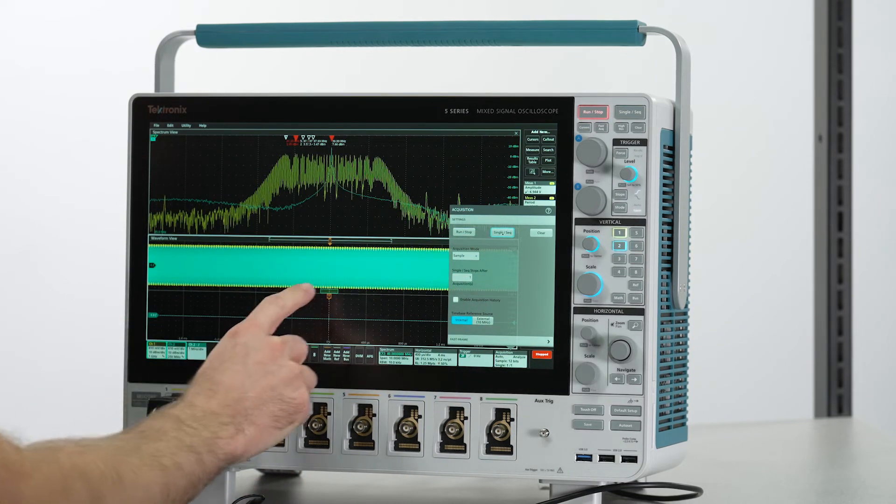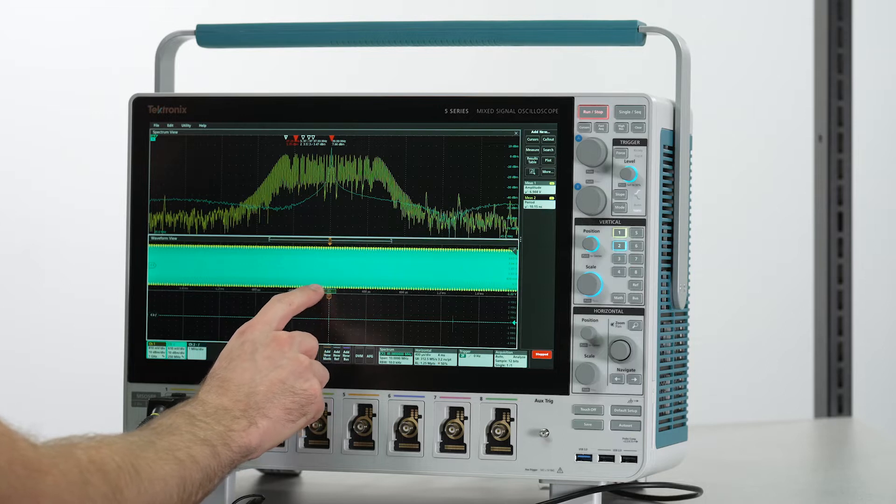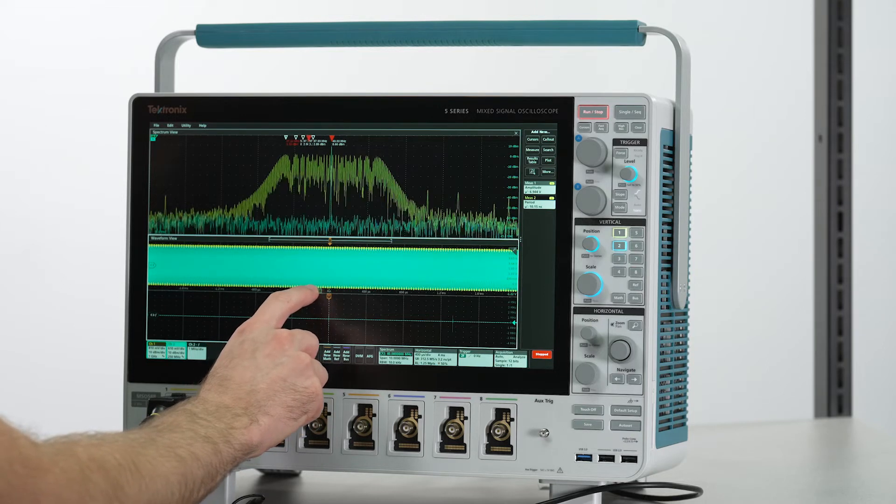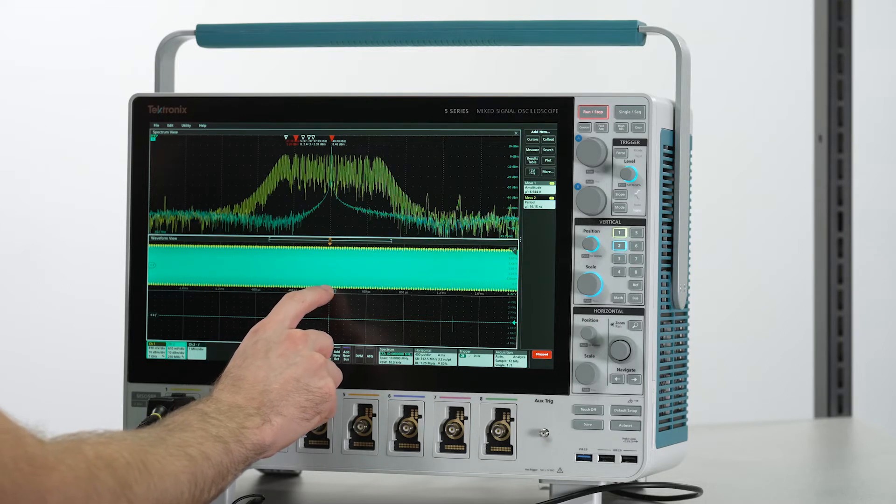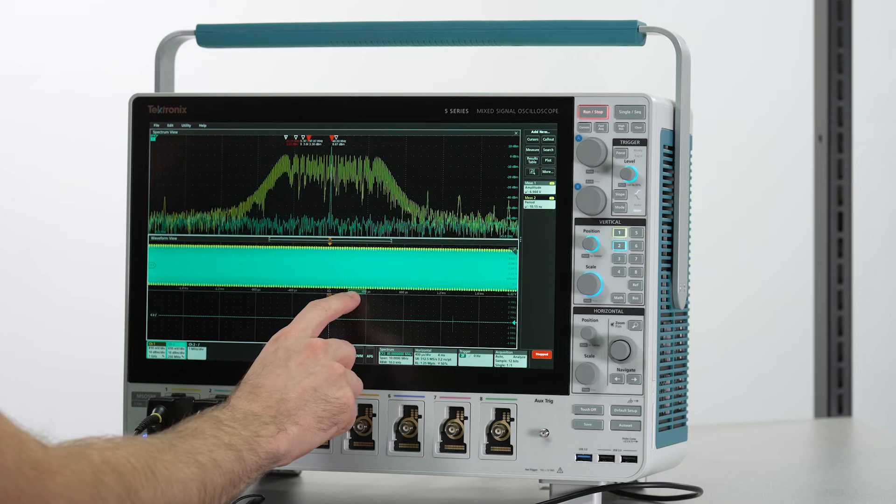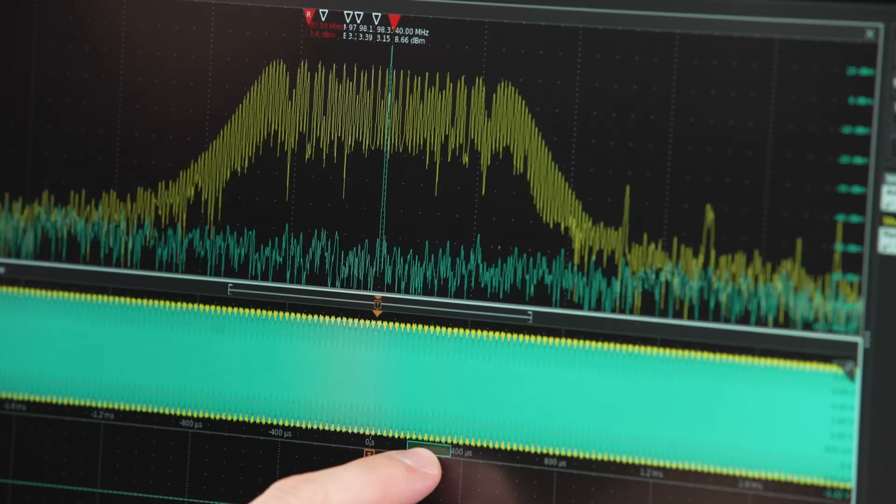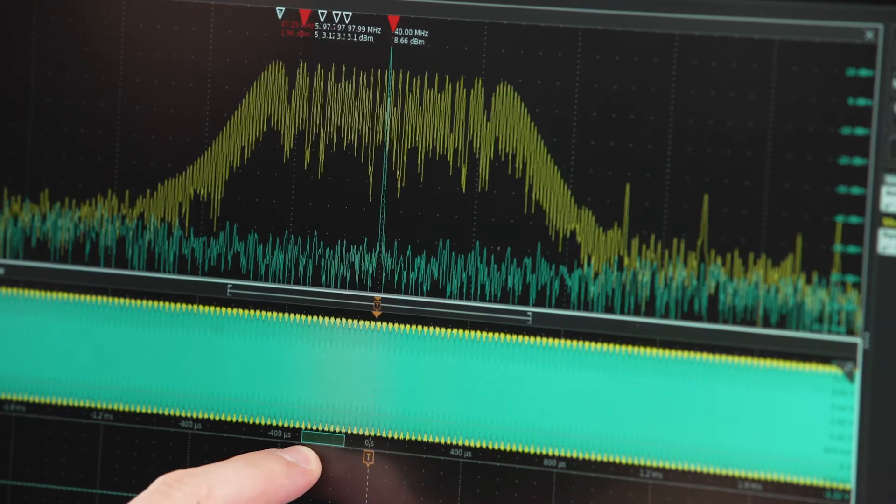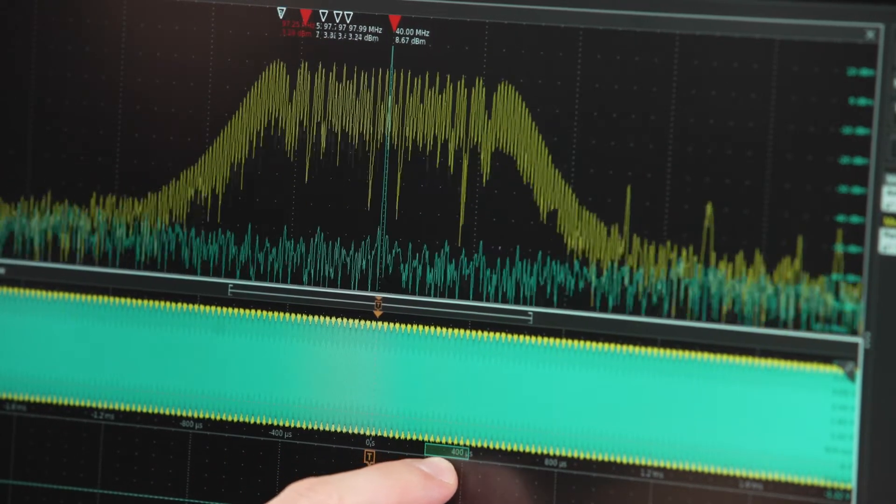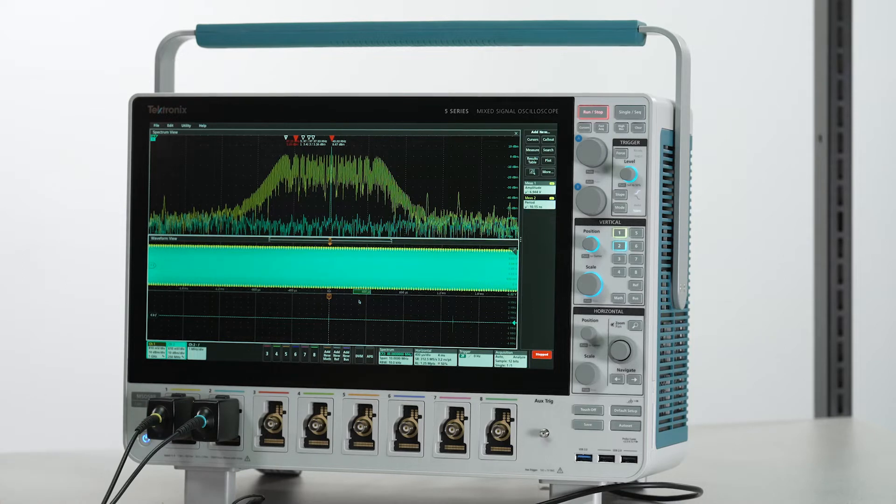This rectangle is called spectrum time and it allows me to select exactly which portion of our acquisition is represented in the spectrum view window. As I drag spectrum time around, the spectrum view window is updated with the RF content derived from this exact time window in our analog acquisition.